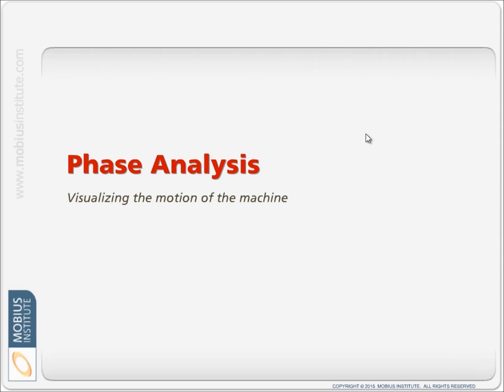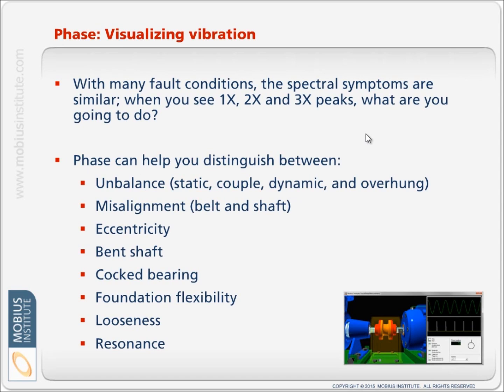Now, phase analysis is an additional type of analysis that tells us much more about the motion of the machine. If a machine's rotor is moving in a circular motion because of unbalance, phase tells us that. If there was misalignment, different sorts of forces, different sort of motion, phase tells us that. Eccentricity, bent shaft, cocked bearing and so on, the phase readings tell us what sort of motion the machine is going through. Therefore we can tell what forces are causing that motion and what sort of fault condition exists.